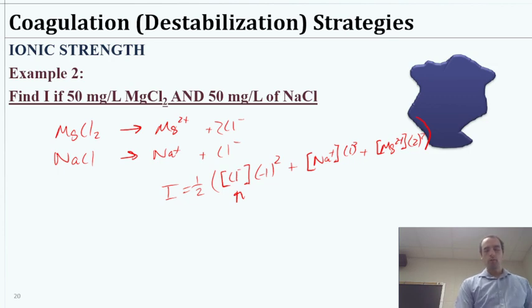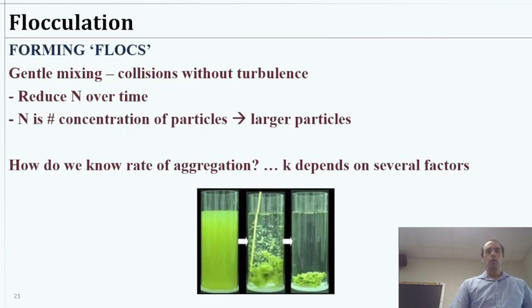Okay, kind of moving on to the last little bit for today. Once we add a coagulant, and I think I'll probably come back to describe a few more coagulants because sometimes we can use other tricks. I mentioned adding ballast like sand to add some density while we're getting them to stick together. You can also use some polymers to reach in and satisfy a charge and then sort of do a bridging thing where the polymer is grabbing that particle and attaching it to other particles with a different arm. So there's different ways we can increase that.